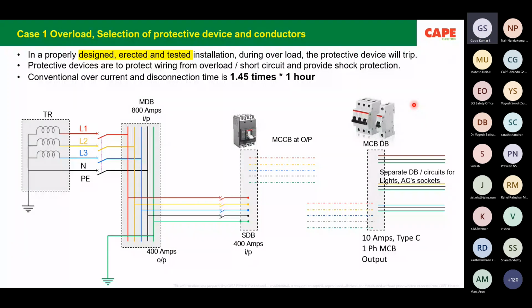Especially if it is a government organization, hospitals, the report always says the fire is due to overload. Actually, electrical engineers shall not use this word overload, because in the circuit we have so many protective devices. As I showed in the picture, there are MCCBs, MCBs, and circuit breakers. All these protective devices are for the purpose of disconnecting the supply before an overload creates a problem. Instead of calling it fire due to overload, we should call it fire due to non-disconnection of the protective device within the specific time.